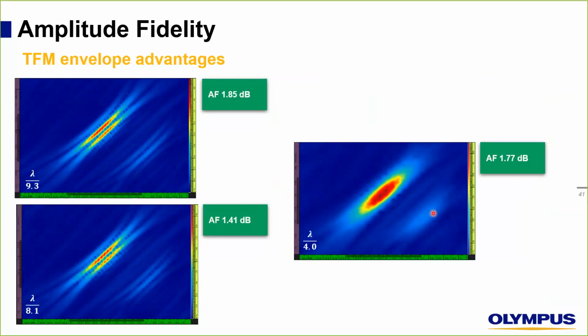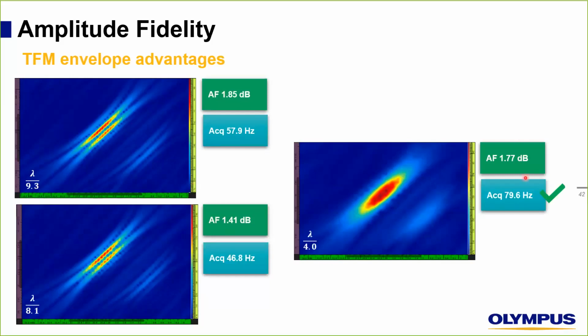Here, because we are discussing the acquisition rate as well, I wanted to show you that for very comparable amplitude fidelity values. So here we have two pictures with no envelope. The first one is at 1.85 dB. The second one is at 1.41 dB with a resolution of 9.3 points per wavelength here and 8.1 there. So if we apply the envelope, we can compare the amplitude fidelity, because they are very comparable. But by applying the envelope, we can reach an acquisition rate of 79.6 compared to 57.9 here and 46.8 here. So the conclusion is that for comparable amplitude fidelity values, or without changing the amplitude fidelity, by applying the envelope, we can increase our acquisition rate.